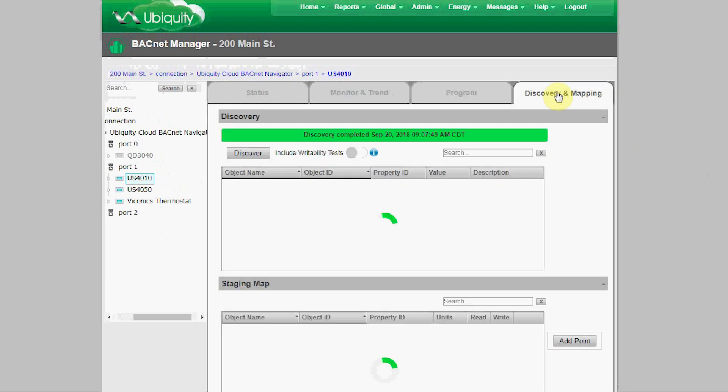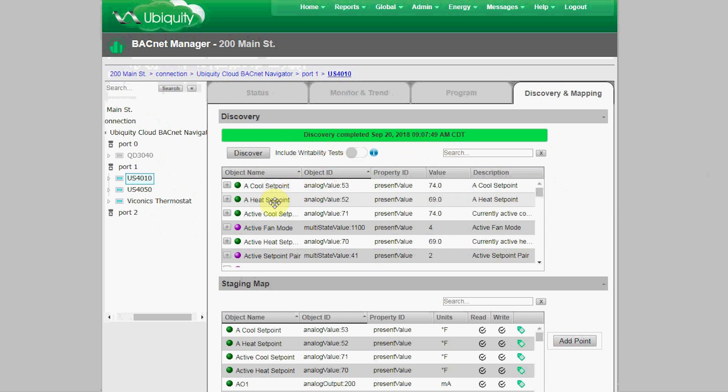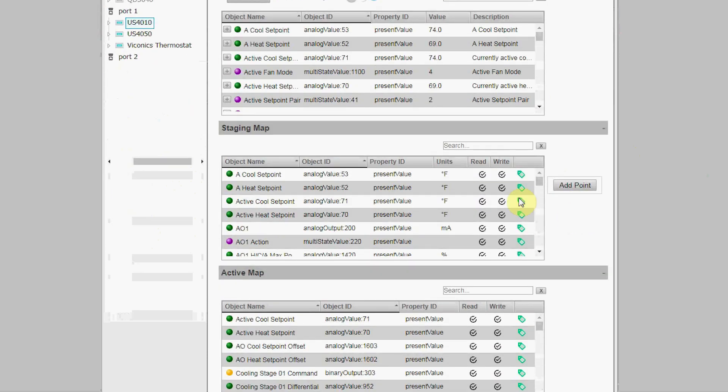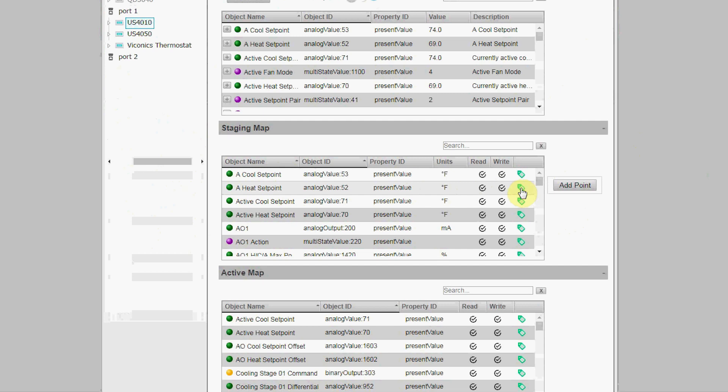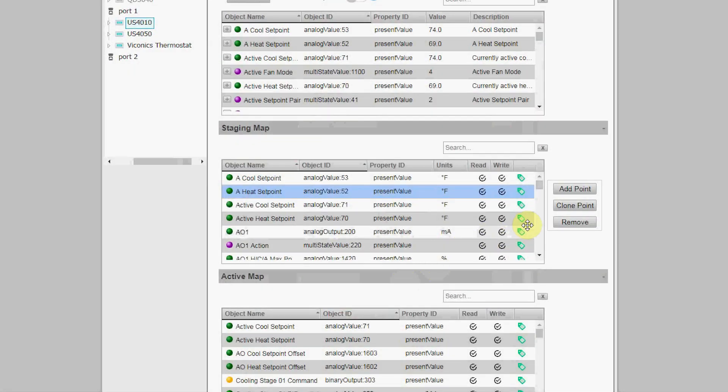The real work is done in the Discovery and Mapping Tool tab. There are three sections on this page. The Discovery section shows the last BACnet discovery that was done and includes all properties and objects for this device. The Staging Map is where discovered objects are dragged and dropped to so they can be properly tagged.